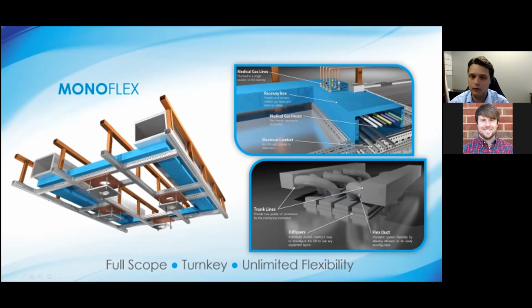The reason we use individually ducted diffusers instead of a plenum is that a plenum inherently limits your flexibility, both during construction and well after. If you put a plenum in that space, you essentially own about 20 inches above the ceiling as just a big air box, which doesn't allow you to change boom locations without going through a redesign.